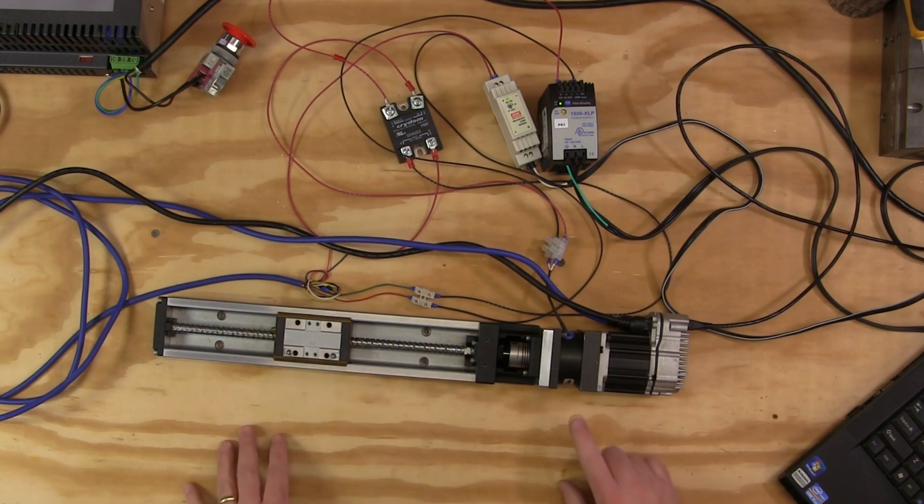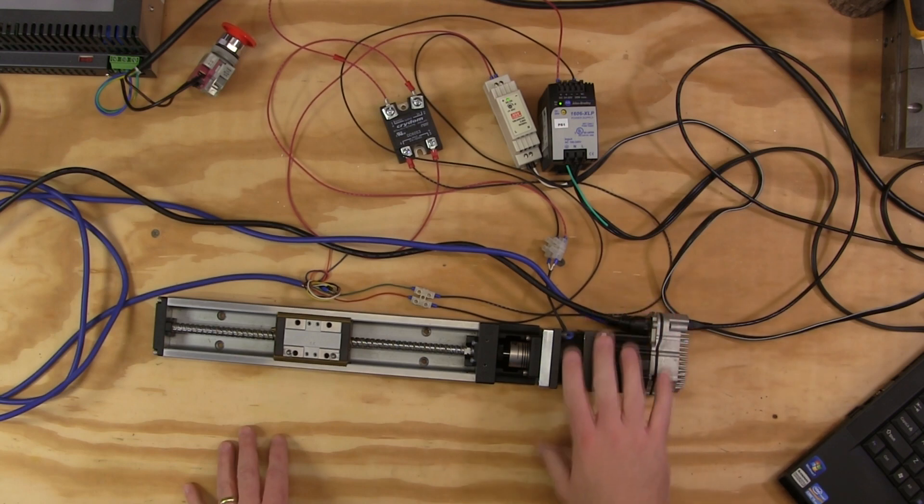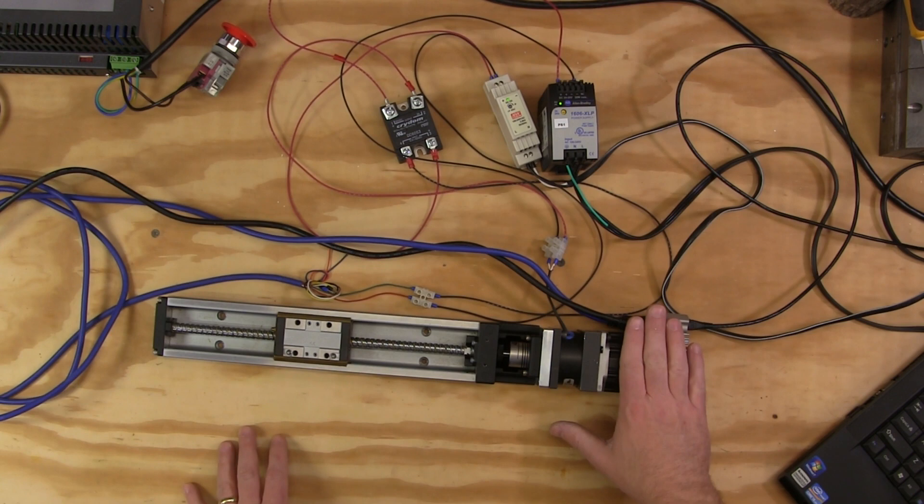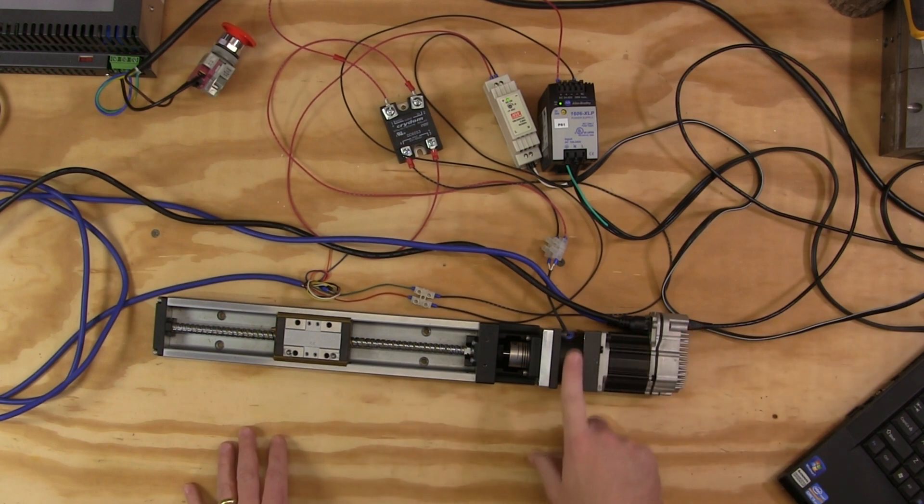Now in this scenario, we've kind of got double protection because if the motor is enabled, it's holding the load and the brake is released. If the motor gets disabled or loses power, then the brake also loses power and it shuts down motion and it does not allow rotation.